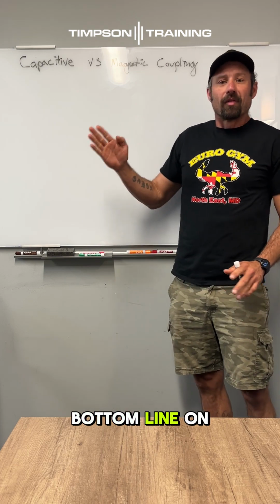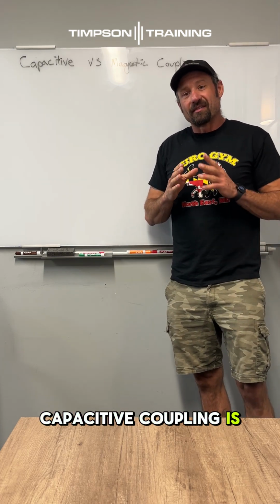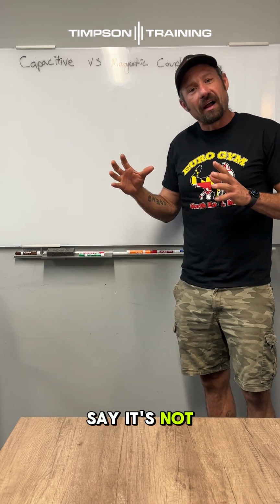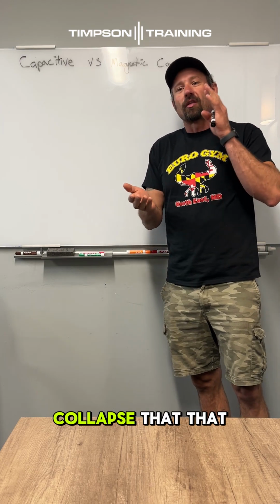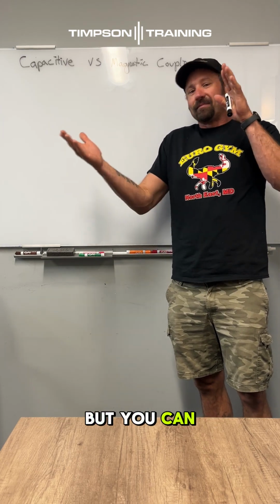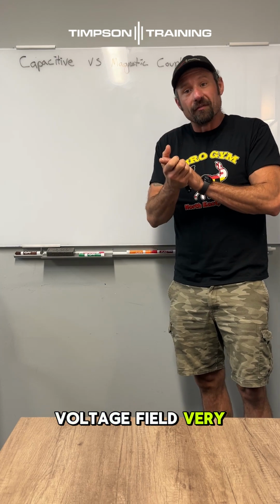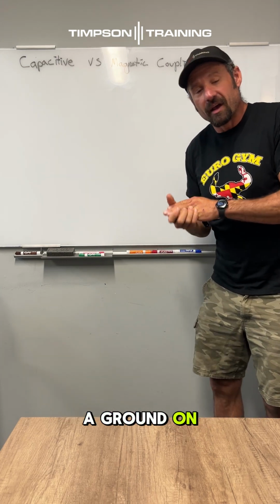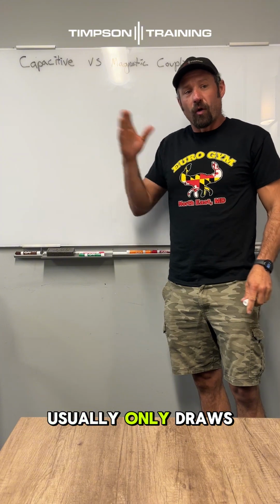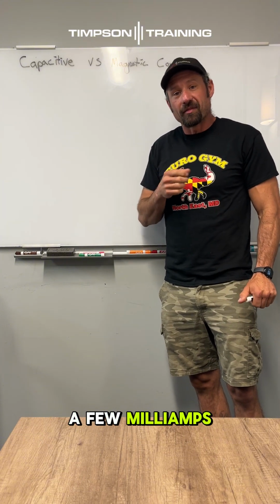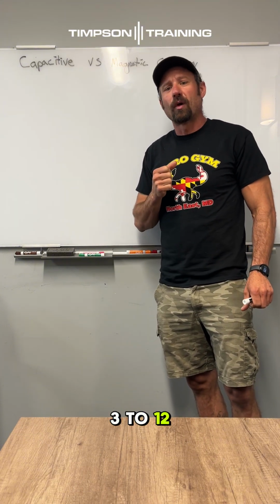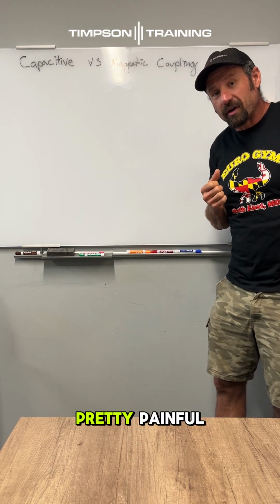But the bottom line on capacitive coupling is, I'm not going to say it's not dangerous, but you can collapse that voltage field very easily by putting a ground on. That ground usually only draws a few milliamps, 2, 3 to 12 milliamps, which would be pretty painful.